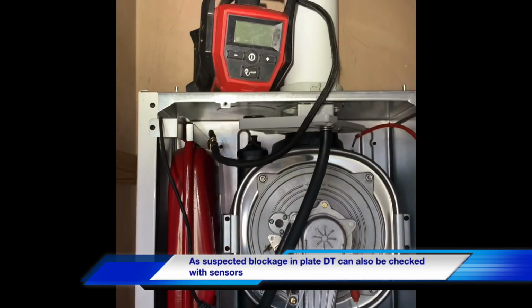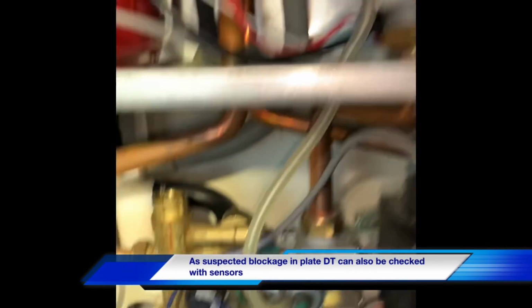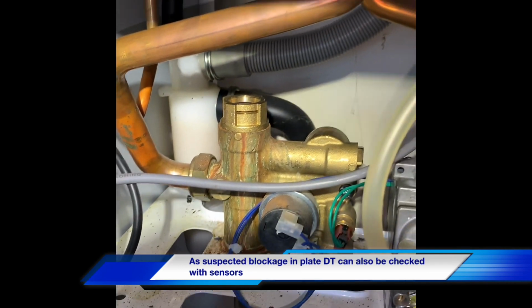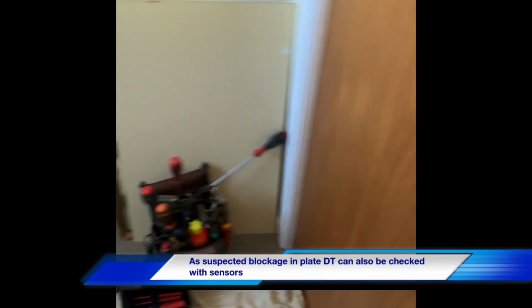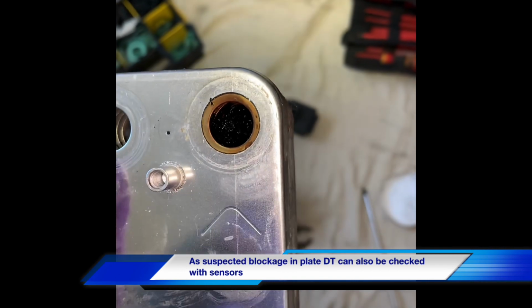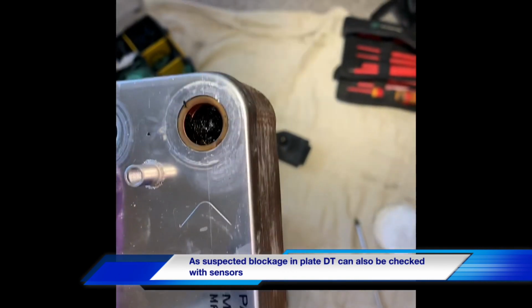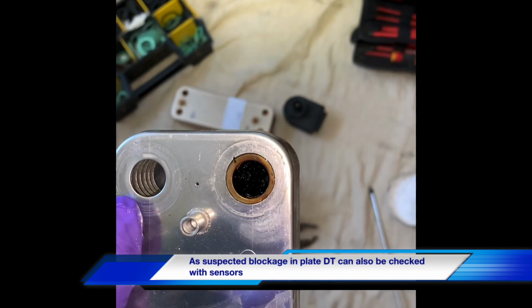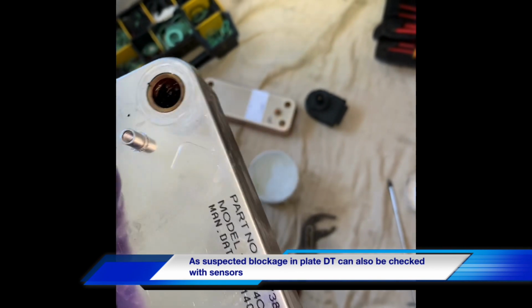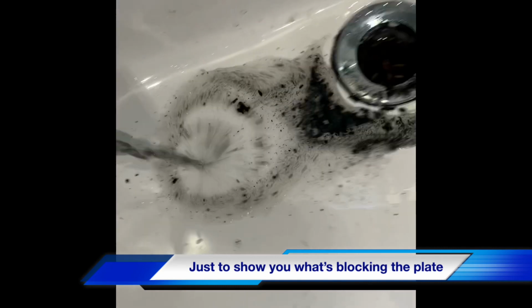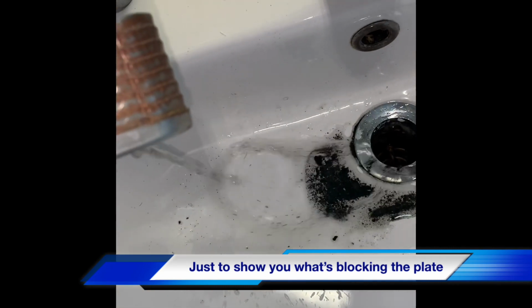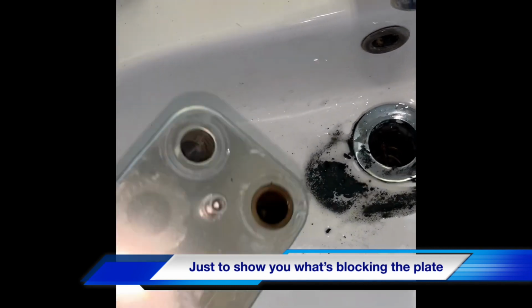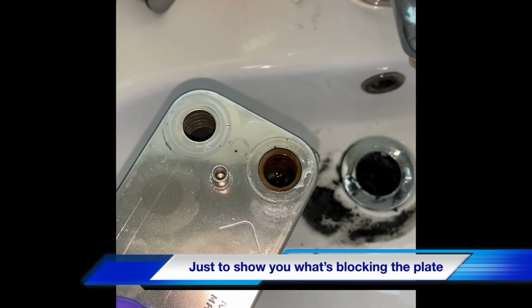So we've recharged the expansion vessel, we've replaced the diverter valve cartridge, we've removed the plate heat exchanger, and as you can see, it is completely blocked inside. So we'll see what little bits we get out of there. That's block solid.